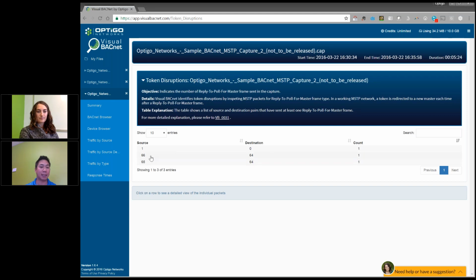We can see 64 asked 66 if it wanted to be master, which for those fairly experienced, you can probably guess that at some point 65 lost the token, got stuck for a while, then 64 took it over again and asked if 66 would be master, then took it over again, went around, and checked if 65 was back after, I think, 50 cycles if I remember correctly. Hence the very long time around the loop.